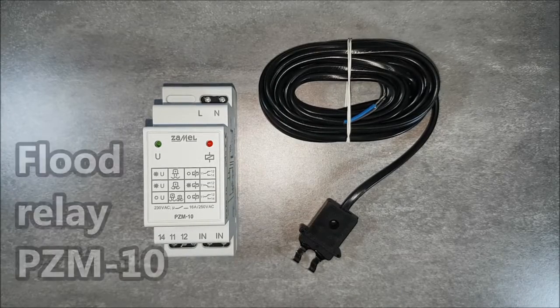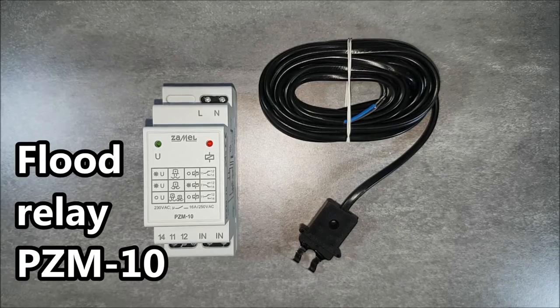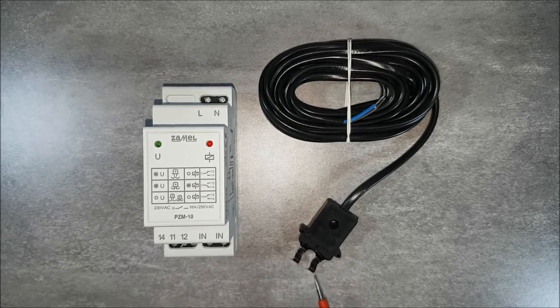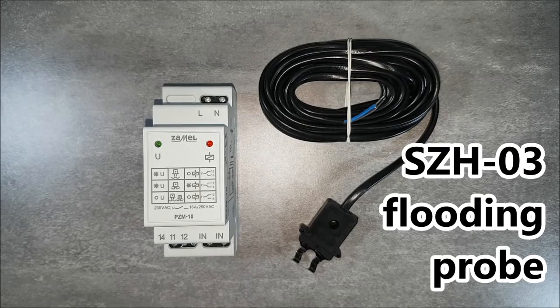PZM-10, the flooding relay, is for detecting the presence of conductive liquids, for example water, at the level of the installed flood probe SZH03. The system can be used to alert about the appearance of water in places exposed to flooding. It can be used in control systems and fluid level control. The external flood probe is galvanically separated, which ensures reliability and safety.